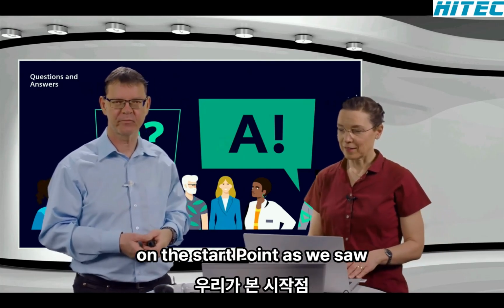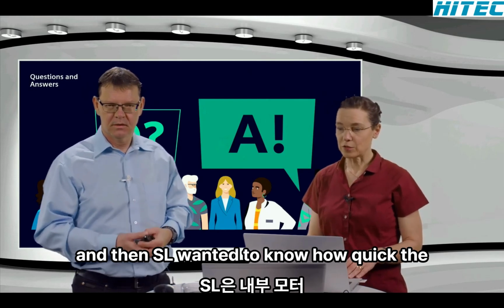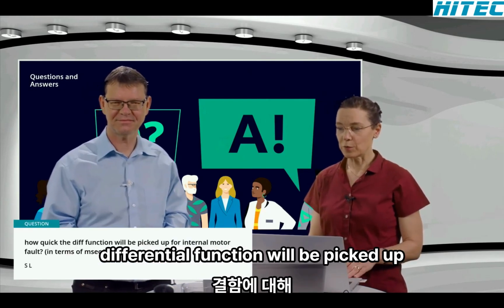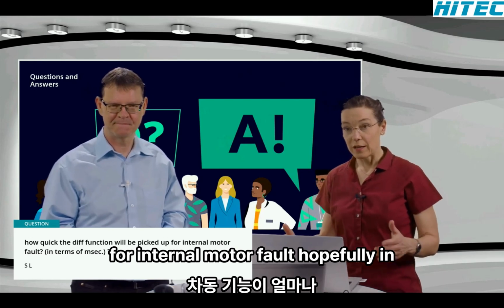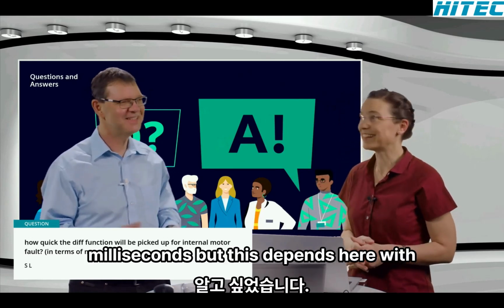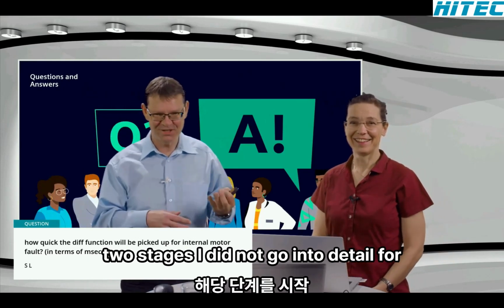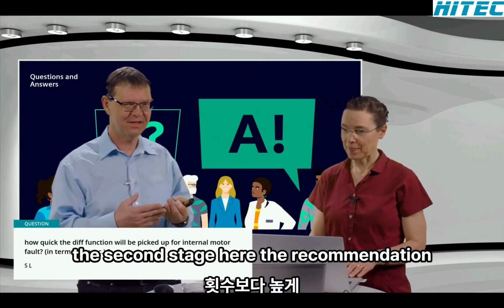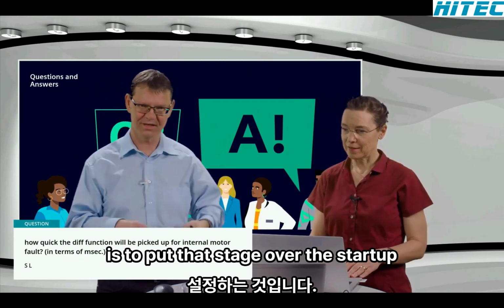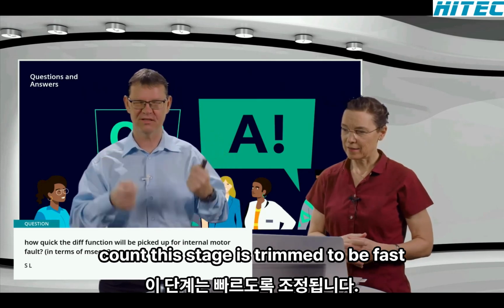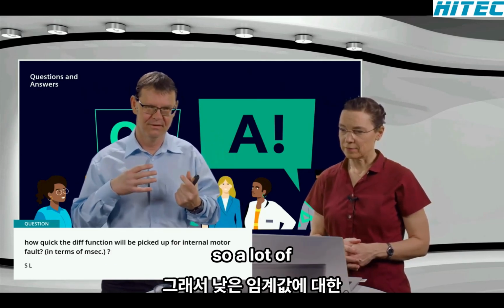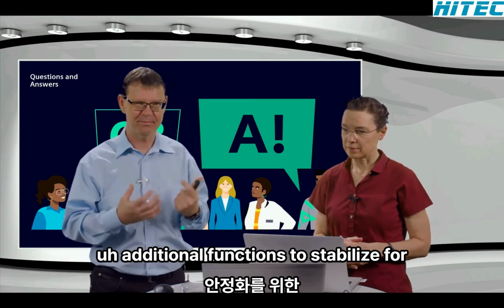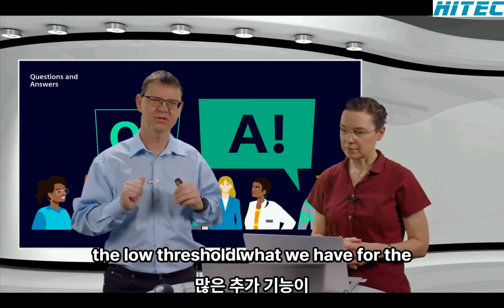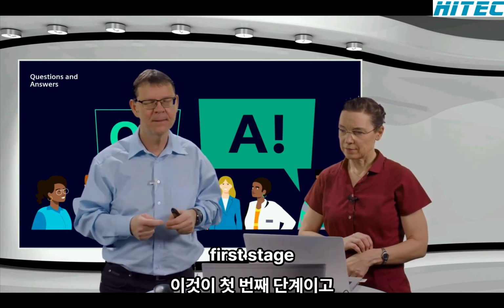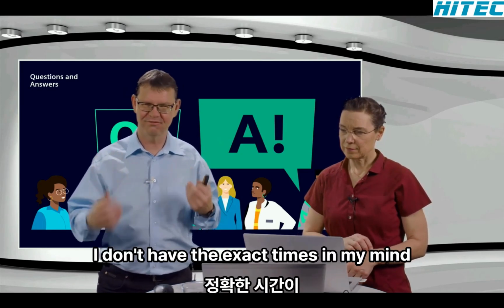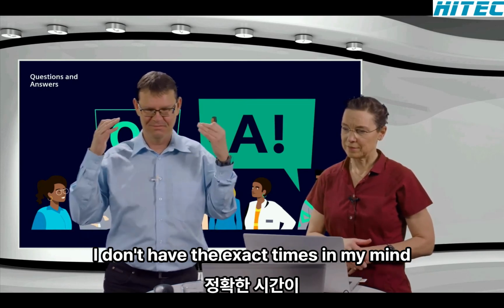Thanks. And then SL wants to know how quick the differential function will be picked up for internal motor fault. Hopefully in terms of milliseconds. Yeah, in terms of milliseconds, but this depends here. We have two stages. I did not go into detail for the second stage. Here the recommendation is to put that stage over the startup count. This stage is trimmed to be fast. So a lot of additional functions to stabilize for the low threshold. What we have for the first stage is not there. So this is the fast stage. And I don't have the exact times in my mind now.